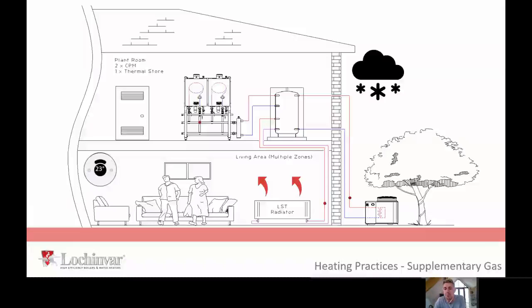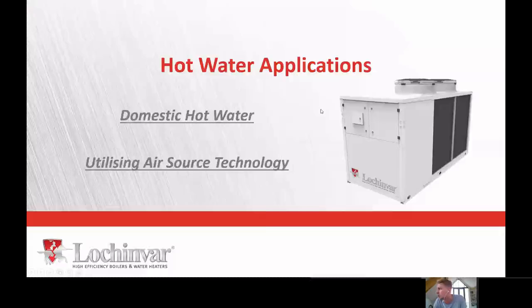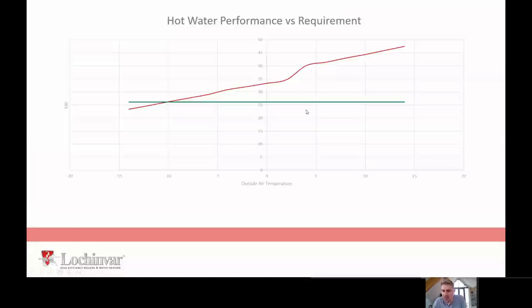Okay, so this is the same sort of story again, but this is going to be for hot water. I'm not going to labour this chart because it's just the same as the one before, same performance ratios. It's just that this time our loading is 26 kilowatts because that just happens to be what we need for a 2-hour heat up time on a 900 litre storage vessel. You just notice that that heat up curve, the green line, hot water is hot water. A 2-hour heat up time is a 2-hour heat up time, regardless of whether it's summer or winter.